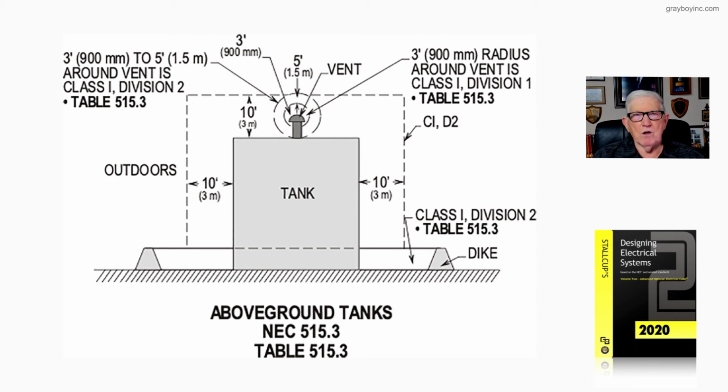So seals are required. But many times out there, if we're not careful, equipment will be built on a rack. The conduit comes out and doesn't go through the ground. It comes out past the dike and then down. And if you don't place a seal there, you're in violation, because you have to place a seal within 10 foot of that boundary in accordance with 501.15 of the code. So keep that in mind, and that's what this figure 21-53 is illustrating.